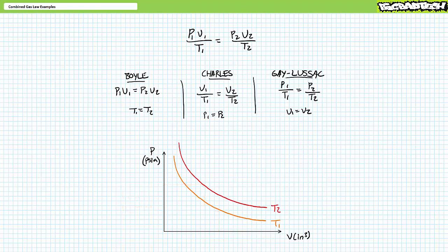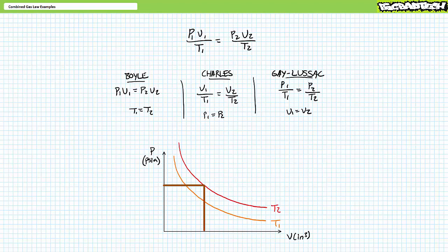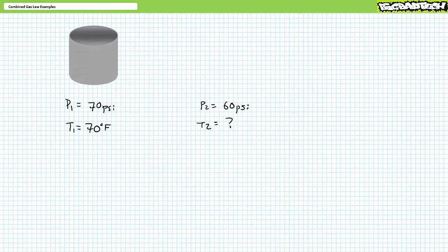What may not be readily apparent is that the temperature rise associated with compression is only temporary. Eventually, whatever you pressurize will cool back down to environmental conditions — back to T1. If done at constant volume in a Gay-Lussac's law fashion, that same volume now exerts less pressure at reduced temperature. This is why you might charge an accumulator to a specified pressure, only to come back after it's cooled down to find pressure has decreased. Even more complex: if volume isn't held constant, you may observe not only a drop in pressure but also a reduction in volume for the same quantity of gas.